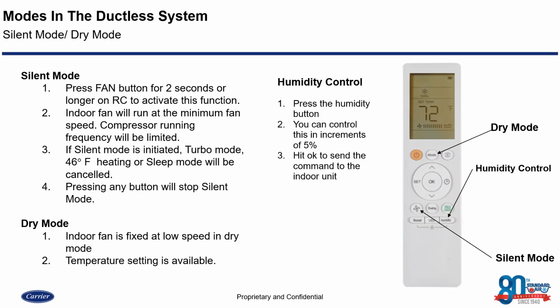Okay. Now, once you've found the percentage that you want to adjust the unit to, go ahead and point the wireless controller at the indoor unit and hit the OK button to send a command to the indoor unit. And what you're listening for is an audible beep to make sure that command was sent and received by that indoor unit. So what this essentially does is allow us to focus not only on the sensible load, but also on the latent load, for a much more precise comfort control for that customer's space and/or spaces.